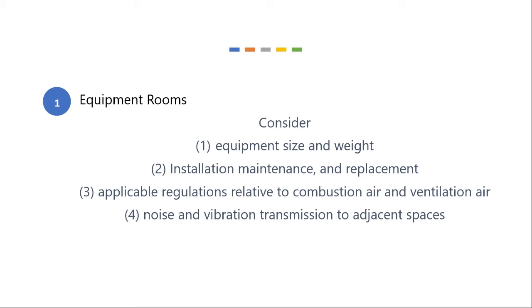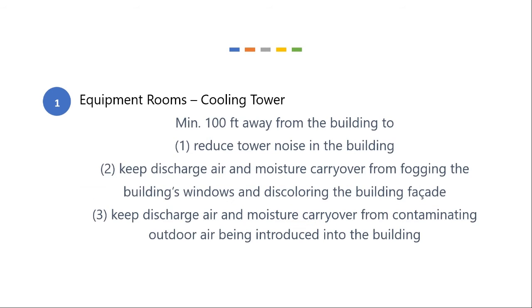Also consider equipment size and weight, installation, maintenance, and replacement, applicable regulations regarding combustion air and ventilation air, and noise and vibration transmission. If you're installing a cooling tower, it should be at least 100 feet away from the building. And that's for several reasons. First of all, it reduces noise. Second, it keeps the discharge air and moisture from carrying over into the building and discoloring the building. Your building will turn orange if the cooling tower is too close.